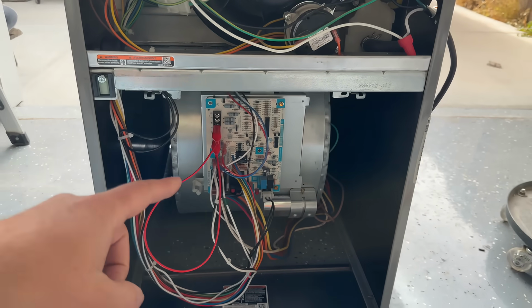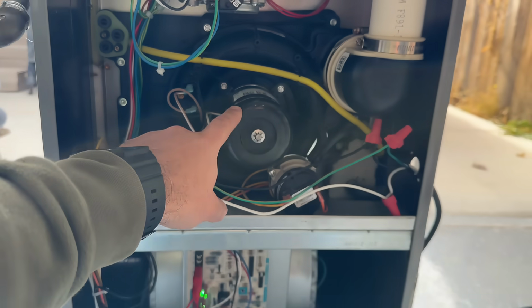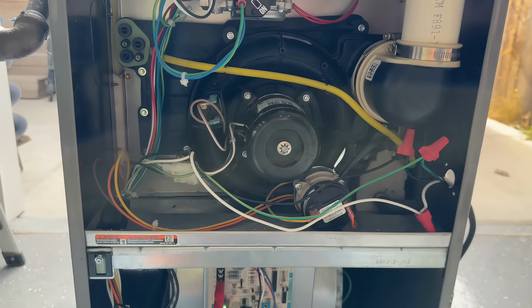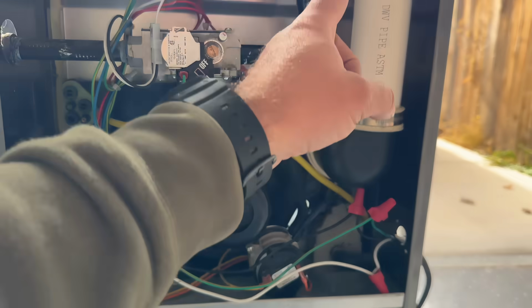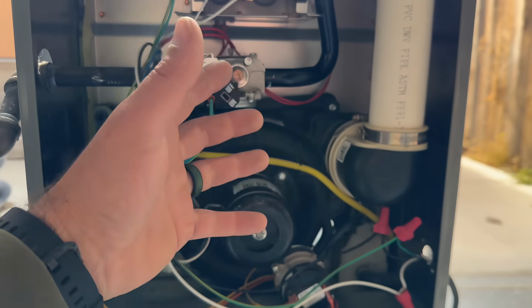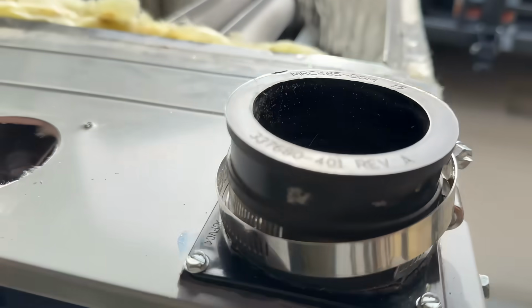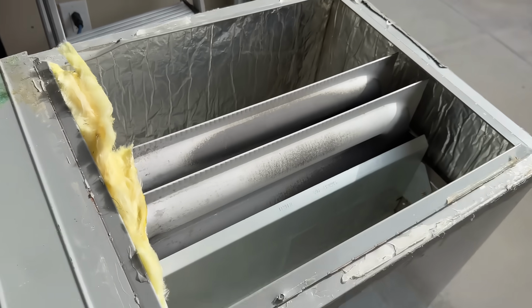So we'll notice here in just a second, the blower will turn off, and immediately after, our inducer will turn on. Now this is the motor that's going to be pulling your exhaust air out of the heat exchanger. And while this is running, I just want to show you what the heat exchanger looks like.